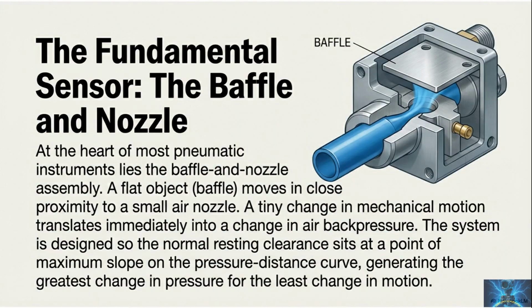The fundamental sensor, the baffle and nozzle. At the heart of most pneumatic instruments is the baffle and nozzle assembly. A small nozzle bleeds air, and a flat plate called the baffle sits very close to it. A tiny change in gap distance causes a big change in nozzle back pressure. That means microscopic motion becomes a measurable pressure signal instantly. These systems are designed so the normal resting gap sits where the pressure changes fastest for the smallest motion.